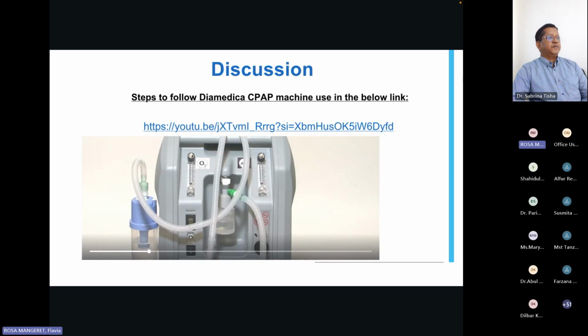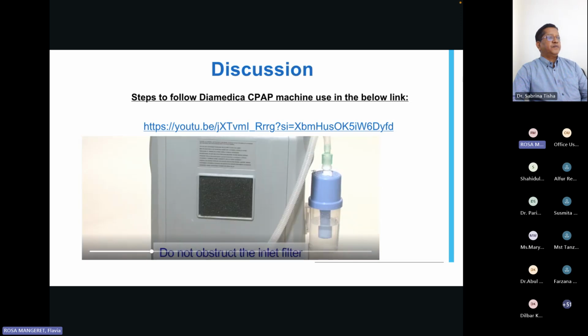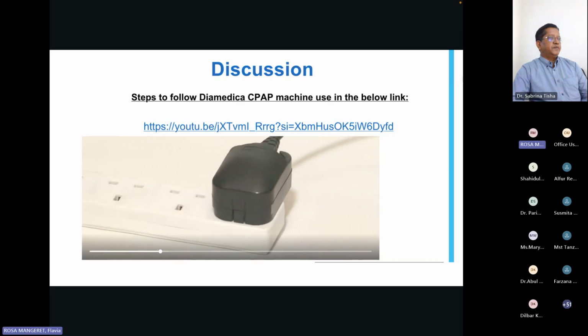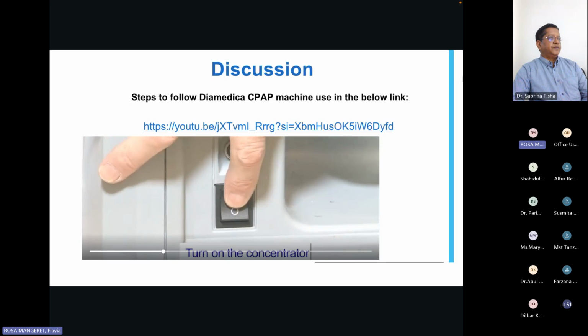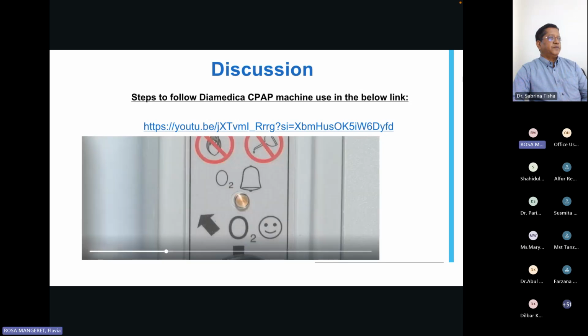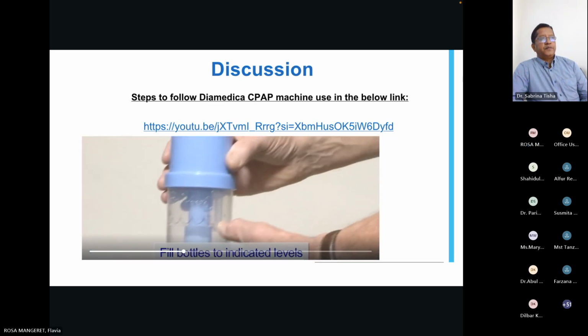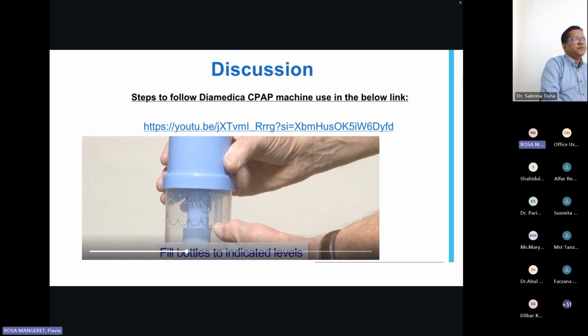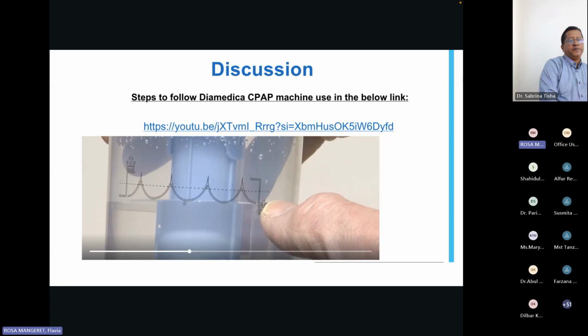Position the concentrator so that it is at least 30 centimeters away from walls or curtains, so that the inlet opening at the back is not obstructed. Plug the power cord into the mains electricity supply and turn on the concentrator. A yellow light should turn on and remain lit for a few minutes, usually within 10 minutes, until the concentration of the gas supplied reaches and exceeds 85%. The yellow light should then turn off after this time, showing that the concentrator is running correctly. Fill the bottles to the level indicated with boiled water that has been allowed to cool and screw the lids back on.